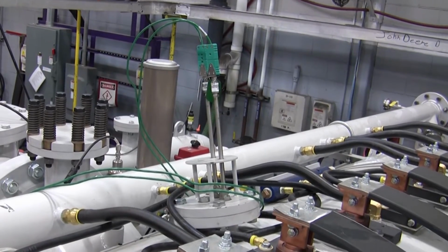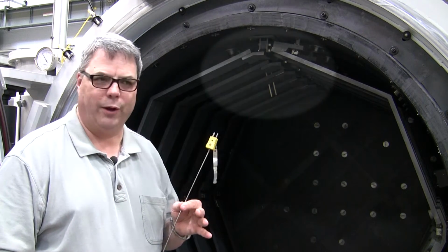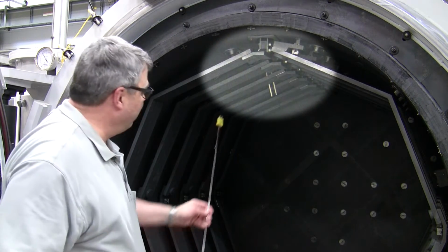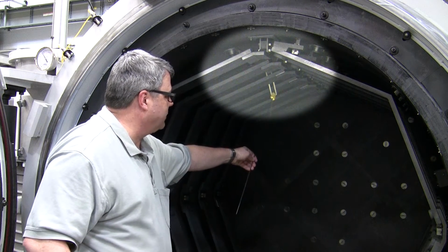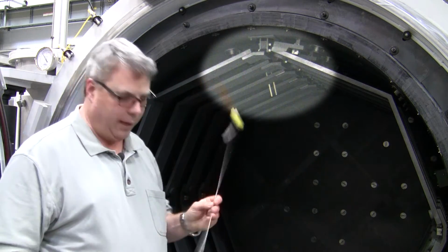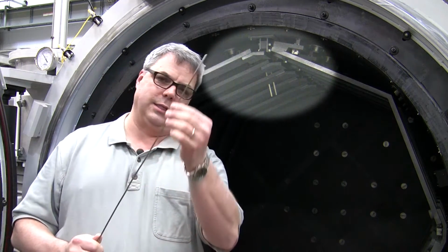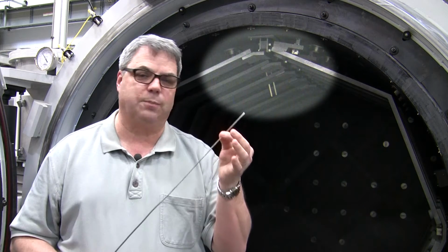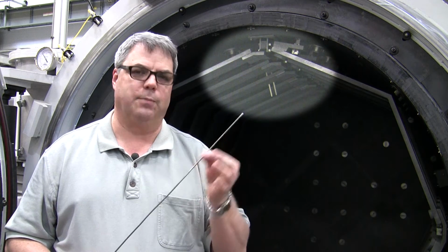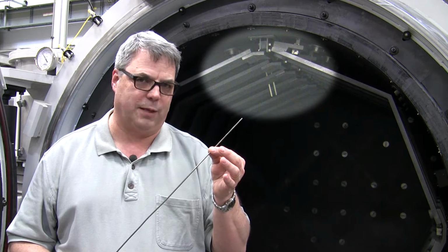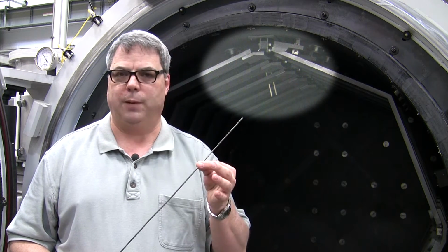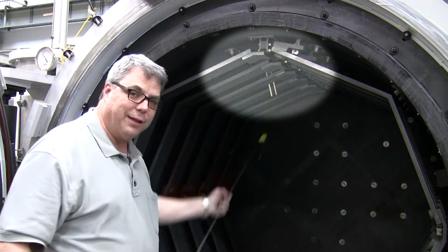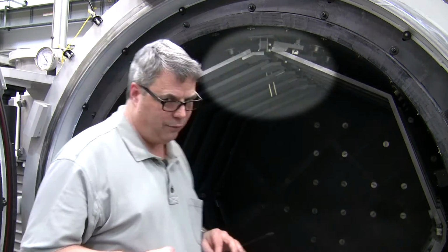Now let's move to the inside of the furnace where we can talk a little more quietly. I'm going to use a type K thermocouple for my pointer and for further reference. So we have our control TC and our overtemp TC, and you notice that they're made out of ceramic. They are not the old-fashioned all-metal TCs, because the old metal TCs don't have the response time for the lower temperatures, and it's much harder to control the furnace and keep uniformity within specification without overshoot for the aerospace and nuclear arena. So our standard was transposed over the years to the ceramic sheath, because everybody knows that the open tip TC is forbidden in 2750.